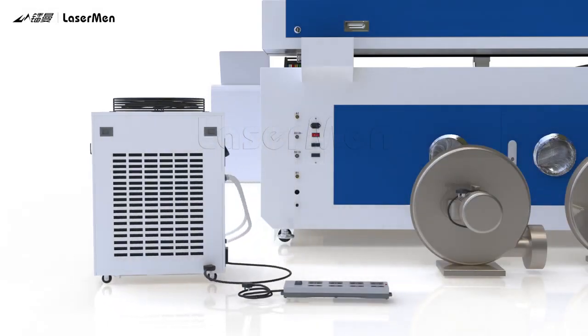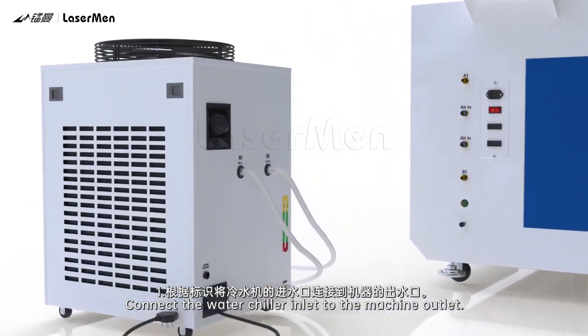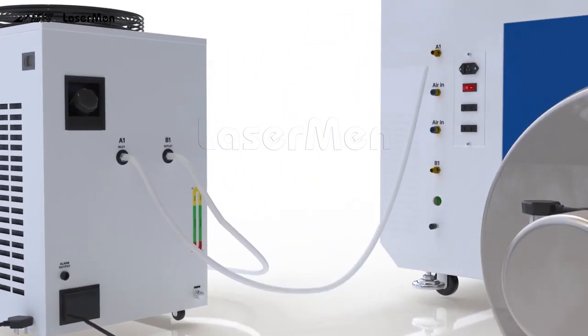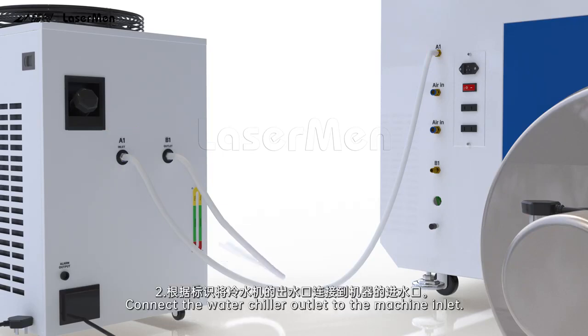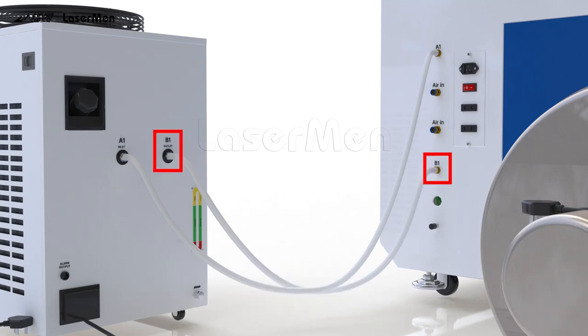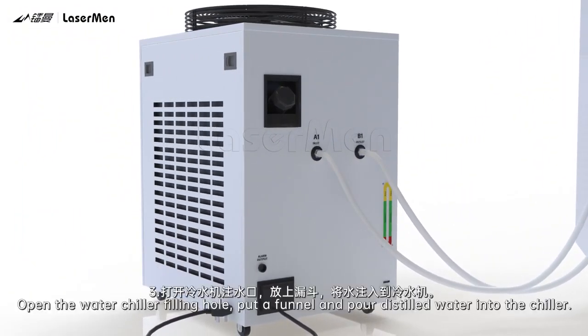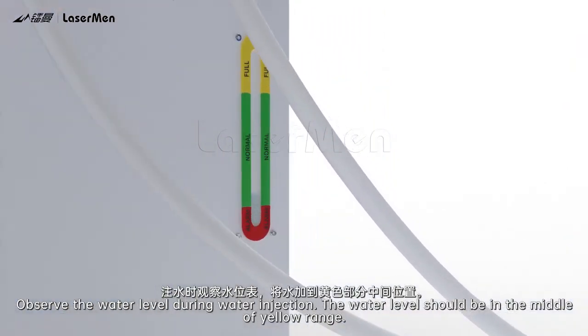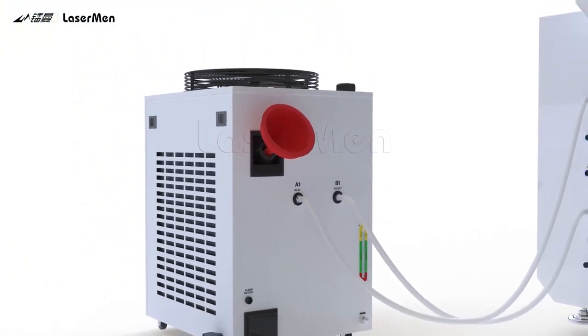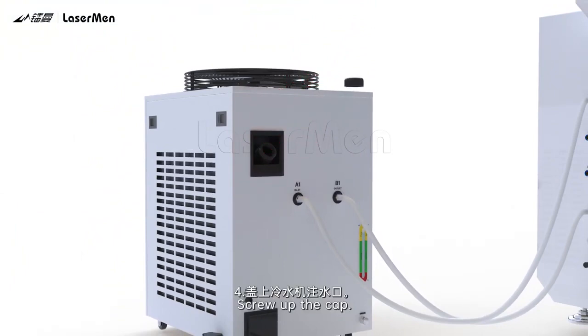Water chiller installation. 1. Connect the water chiller inlet to the machine outlet. 2. Connect the water chiller outlet to the machine inlet. 3. Open the water chiller filling hole. Put a funnel and pour distilled water into the chiller. Observe the water level during water injection. The water level should be in the middle of yellow range. 4. Screw up the cap.